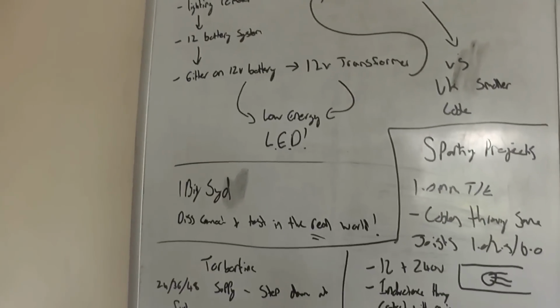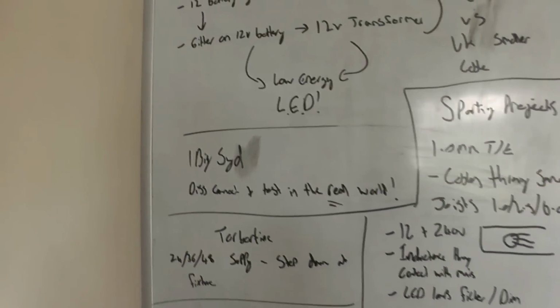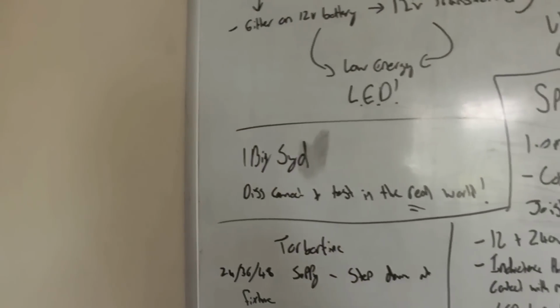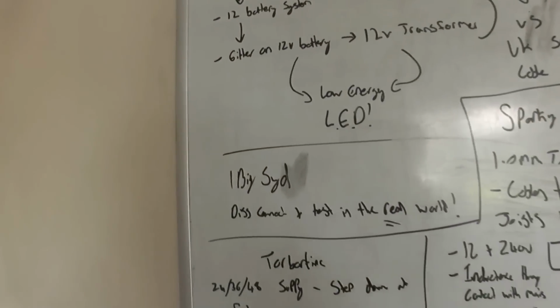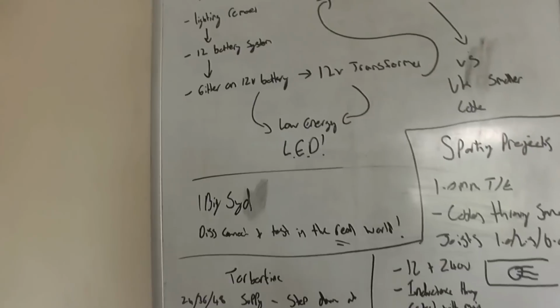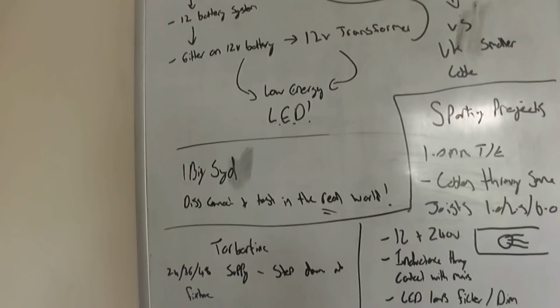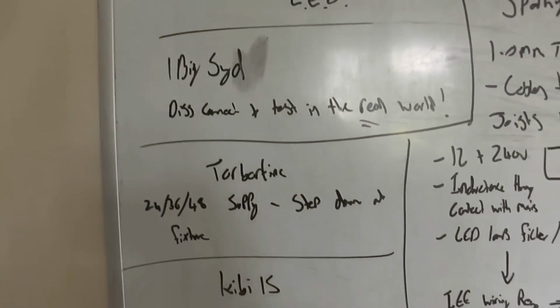If they're all, say, batten fittings or pendants, then I would certainly test. I may be able to do a test. It may just involve testing R2, taking that as a rough number. Obviously that's forgetting going to the switch and back. But just to get a rough idea, I might do a long lead test and just get R2 and give us something to think about.